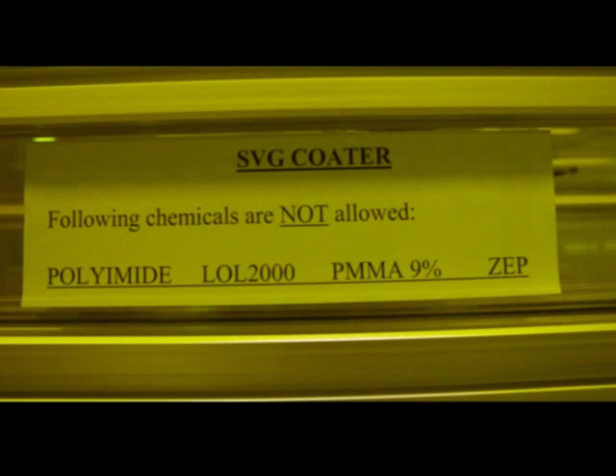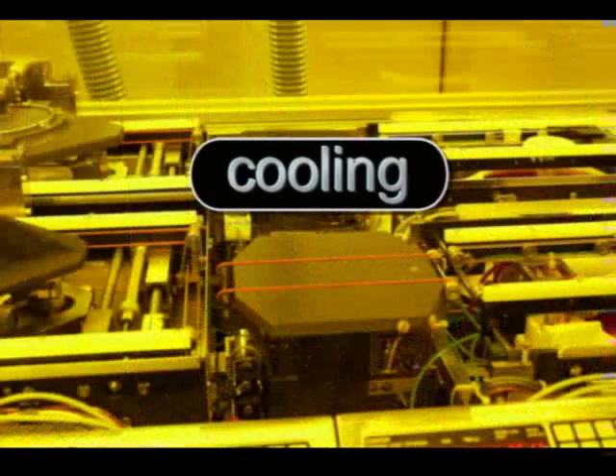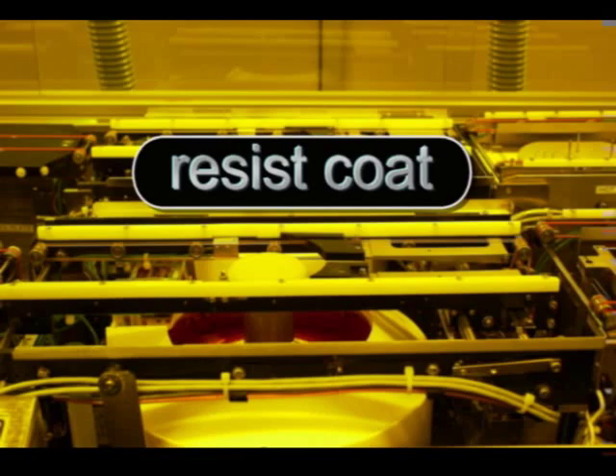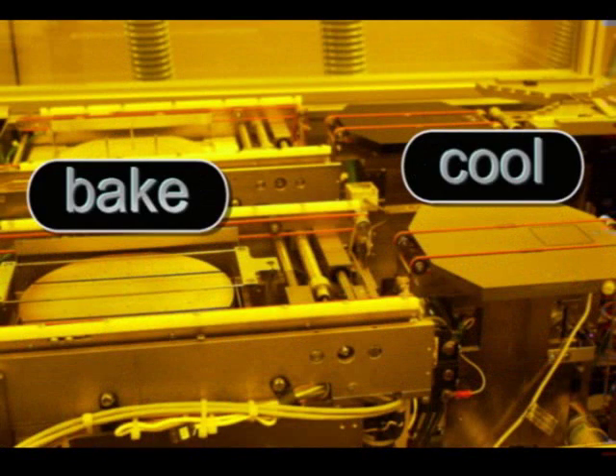For polyimide, LOL2000, PMMA 950K 9%, or ZEP, please use the headway coater. To give a brief overview, both tracks have cassette loading, HMDS vapor prime, cooling stations, resist coat, and bake and cool stations.